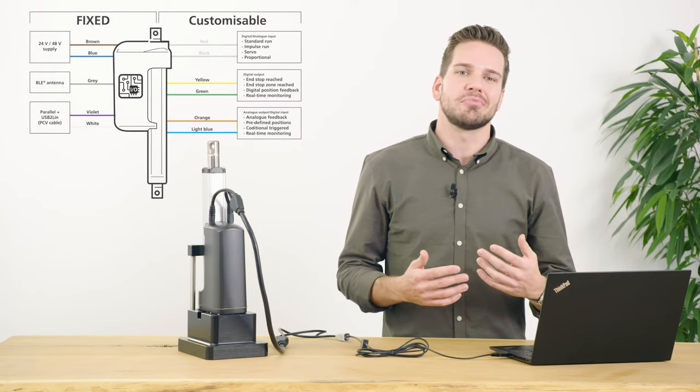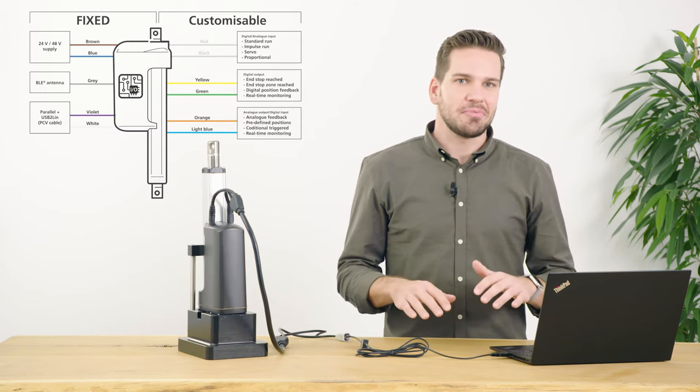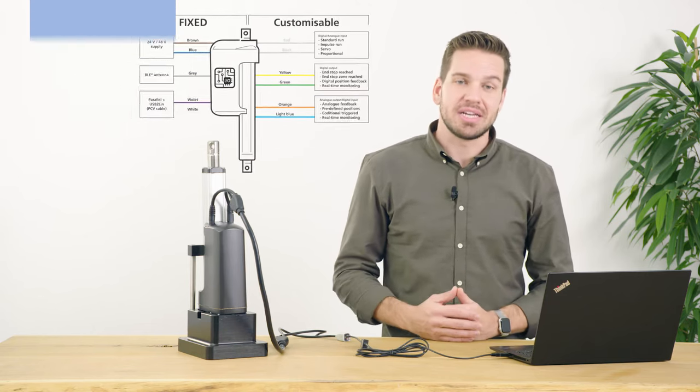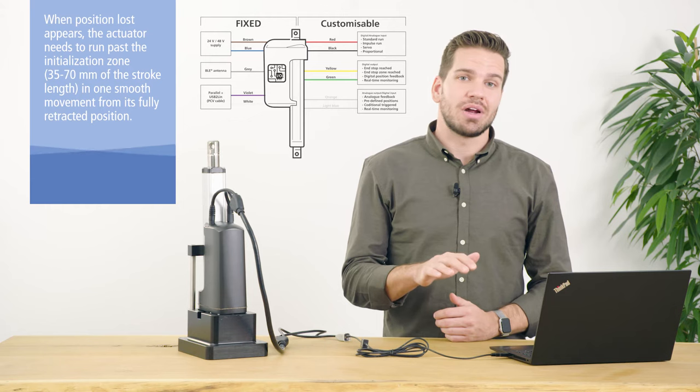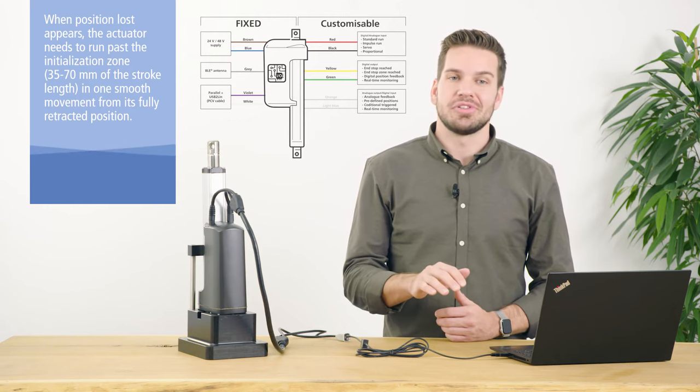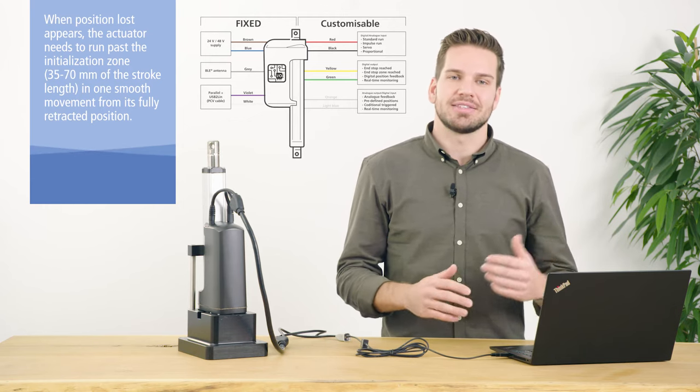If the actuator experiences a position lost error, the orange and light blue wires used for predefined positions can no longer be used to drive the actuator. Because of this, the red and black wires are reserved for standard run so that the actuator can be re-initialized.